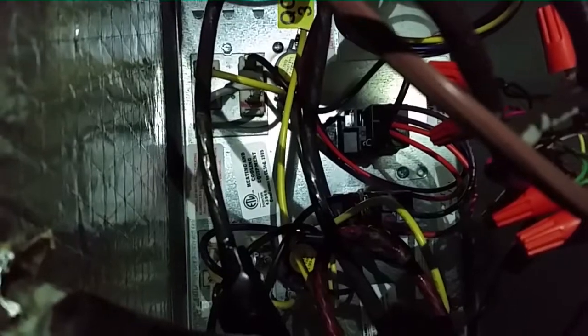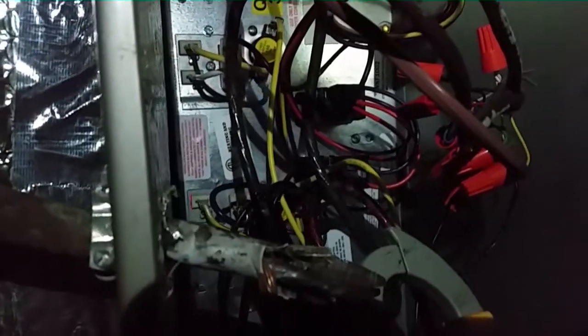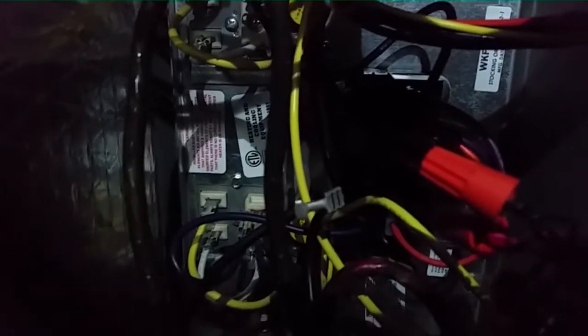And I looked inside there all of a sudden, and I see on that relay, I'm gonna hold it real still so I can highlight it, you can see that there's no wire on it. And I looked around inside there, it's hard to see down in there, but the wire is actually dangling. So we need to turn this off right away, get that thing plugged in right, and check it again. It's hard for me to get my hand in there. Look at that. It fell off. So we're going to plug this back in up here.